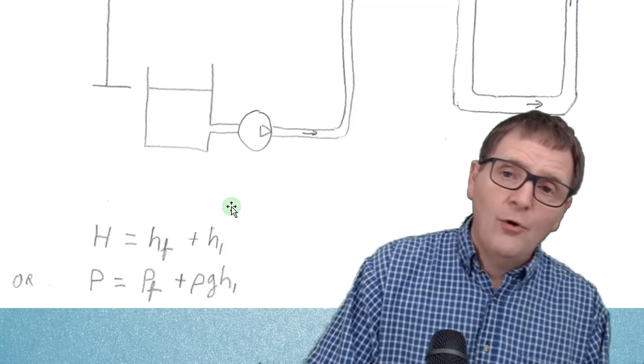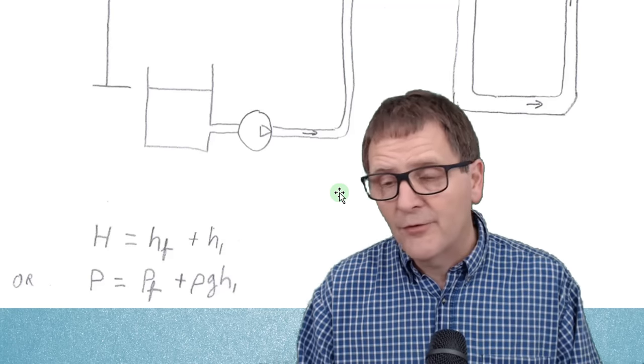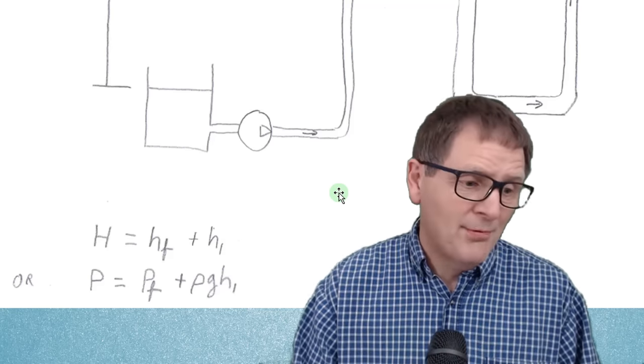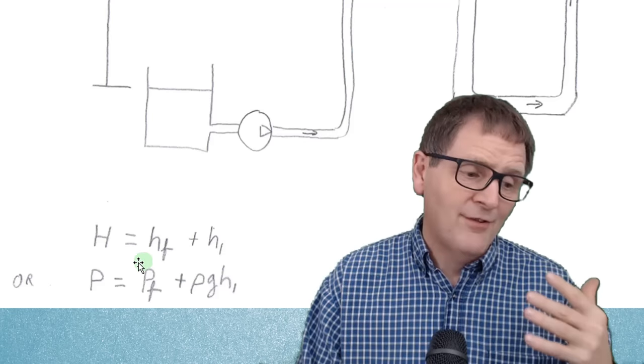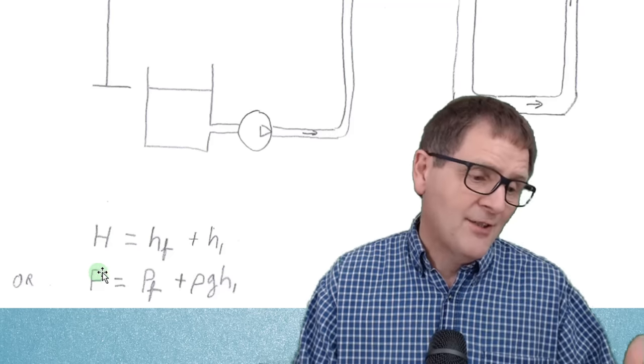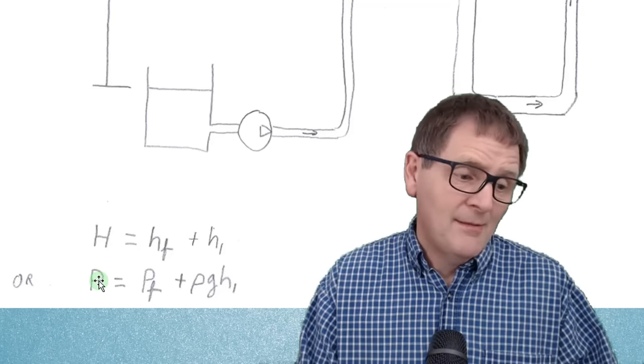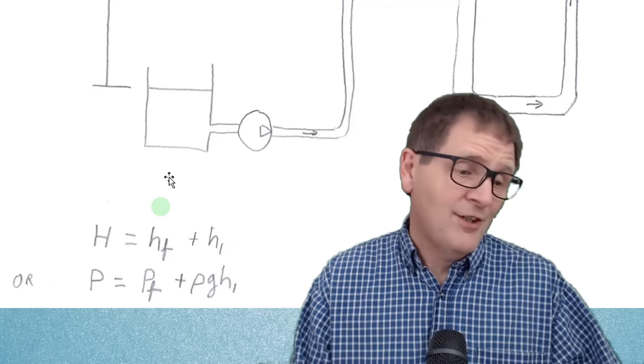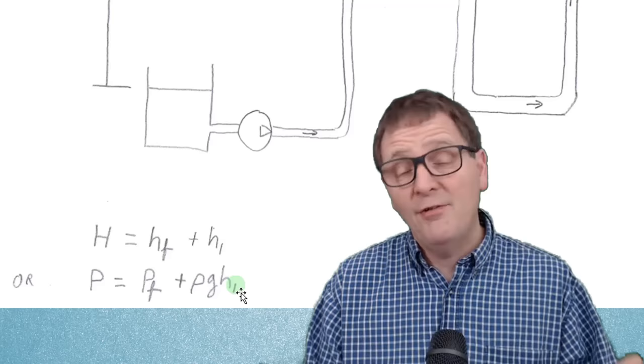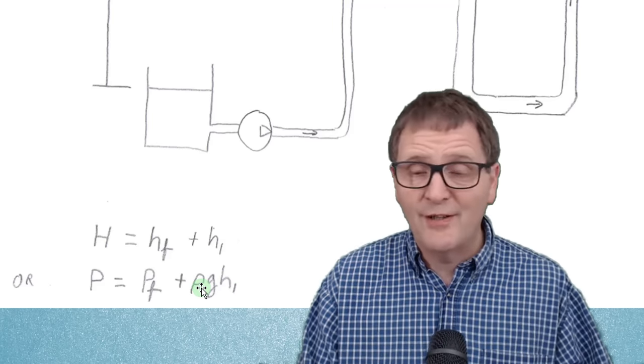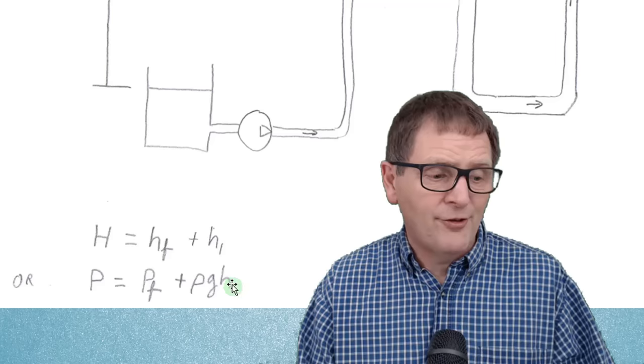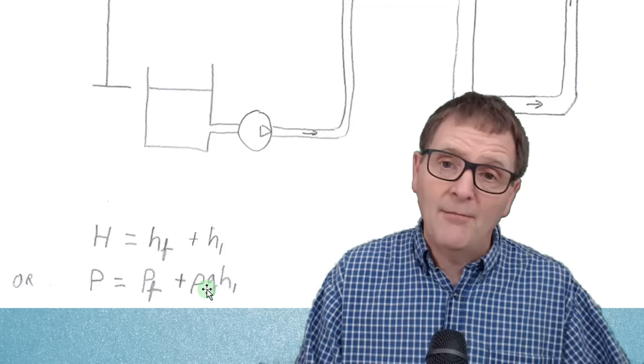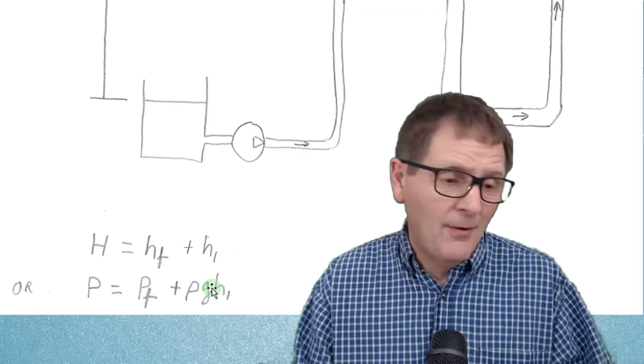Normally with water hydraulic systems you talk in terms of head, but for other applications you might want to talk in terms of pressure — pressure and head are much the same thing, just different units. In terms of pressure, the total pressure equals the friction pressure loss plus ρgH1, where ρ is the density of the fluid, g is the gravitational constant, and for water the density is around 1000 kg/m³ and gravity is 9.81 m/s².